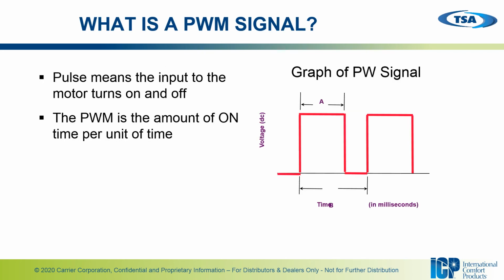Okay, this is an example of the pulse width modulation signal. As I discussed before, the pulse means that the input to the motor turns on and off. And oftentimes, this signal is happening so fast that a meter cannot pick it up, in which case the meter will average the voltage out and you will see a solid voltage reading.